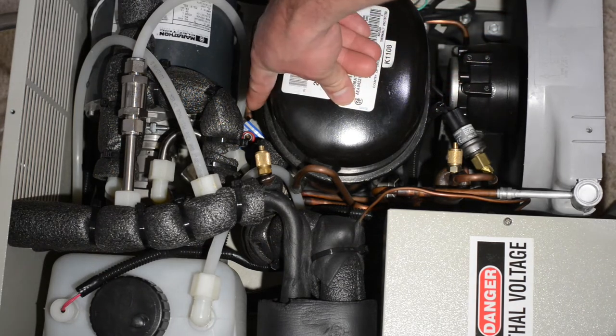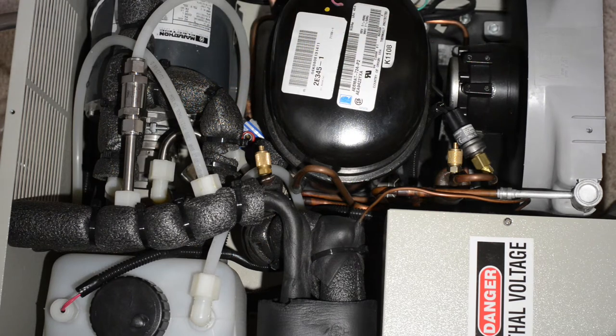And then down here we have a solenoid valve. What the solenoid valve does is it opens up periodically to allow refrigerant to flow past the water to refrigerant heat exchanger and straight back into the compressor. That means that it's not doing any cooling during that time and allows for the temperature to be regulated via the PID controller on the front.